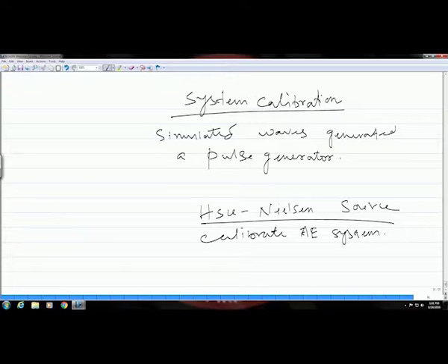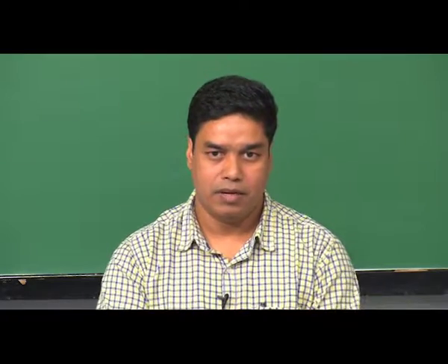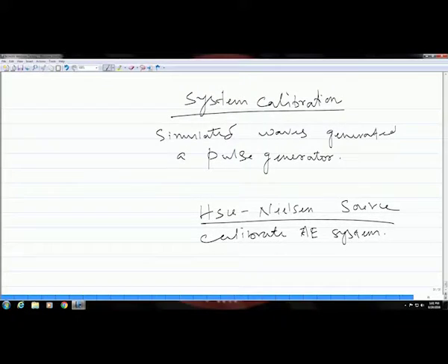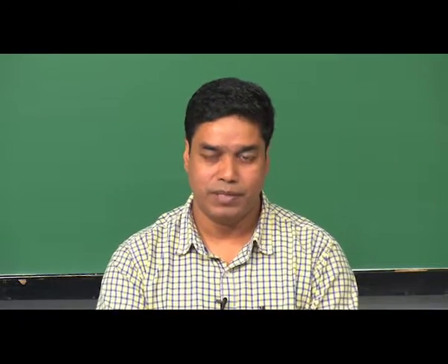This is a very simple method, but still quite effective. You do not really need a high end instrument or expensive pulse generator and things like that. What you need is something which can generate these acoustic emission events, like what you get from damages or defects inside a component.